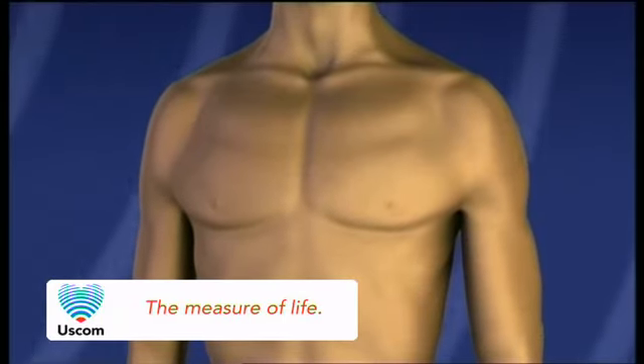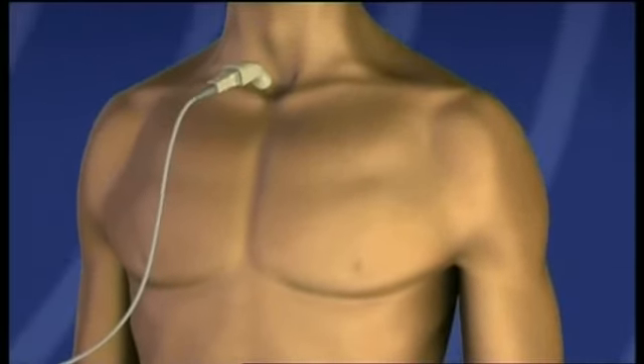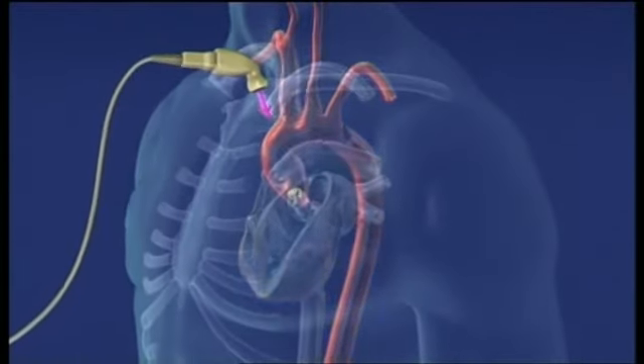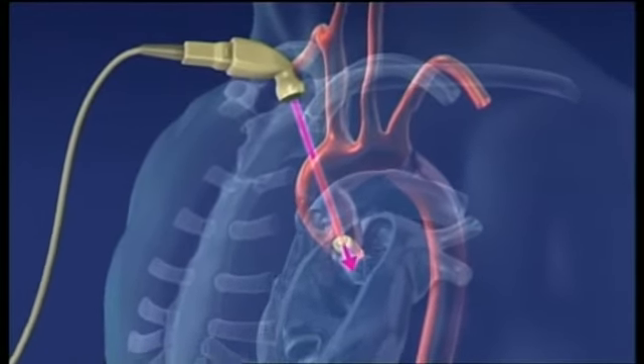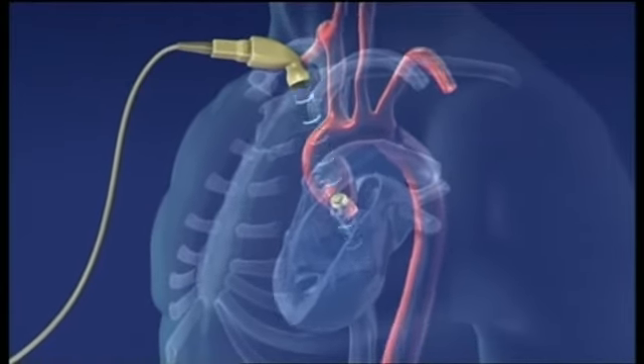To calculate left cardiac output using the USCOM ultrasonic cardiac output monitor, a small non-invasive probe is placed in the suprasternal notch, aiming directly down the longitudinal axis of the ascending aorta and across the aortic valve. Using USCOM's beam acoustics technology, the probe emits a very broad continuous wave Doppler ultrasound signal, which is used to calculate the ejection velocity of blood as it exits the aortic valve.